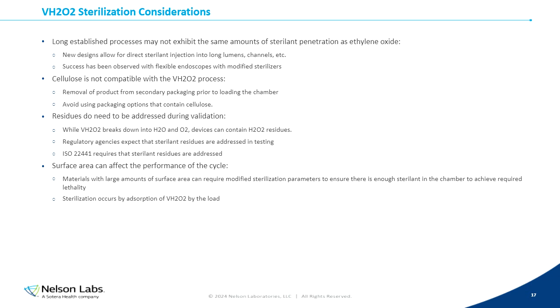Finally, I would like to just mention some vaporized hydrogen peroxide considerations. Some of these we already touched on and others maybe not, but let's just quickly go through the list. Some of the older vaporized hydrogen peroxide processes may not exhibit the same amount of sterilant penetration as ethylene oxide. I have seen this in testing where some more complex devices might struggle through some of the healthcare cycles that are long established. It may be hard to achieve required sterility assurance levels if you have a very complex device. So, that should be considered.